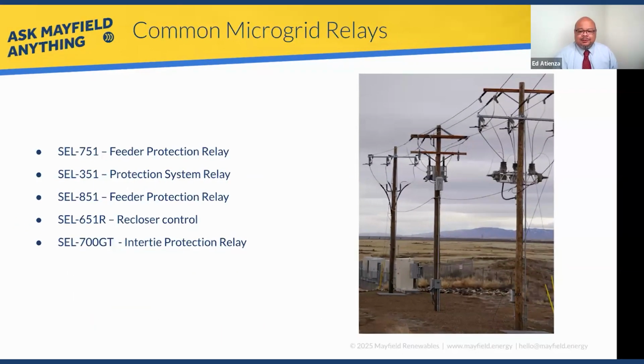Out of this list, we only had the 351. I feel like a lot of applications for DER interconnection probably have the 351, because that's what everyone had for feeder protection, transformer protection, interconnection protection, and sync check, reclosing. It's very widely used because of the functions in the 351, and it specifically has the voltage elements, frequency elements, and sync check elements important to interconnections.